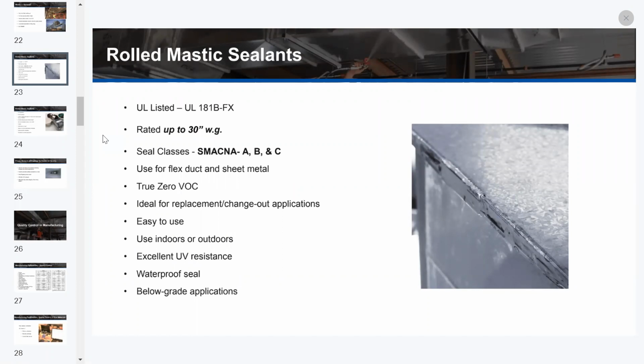Moving on to rolled mastic sealants. They have the following characteristics. They are UL listed, typically UL 181 BFX. They are rated up to 30 inches of water gauge. And that's actually the way we test that: over a 1-inch diameter hole at 30 plus inches of water gauge for a solid 24 hours. Meets all seal classes then, SMACNA A, B, and C. Use it for flex duct and sheet metal.